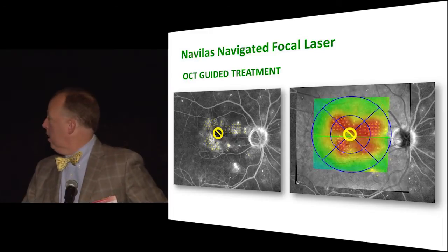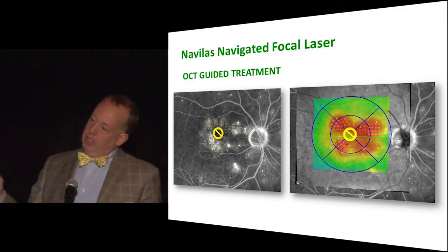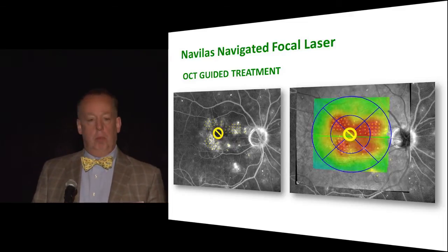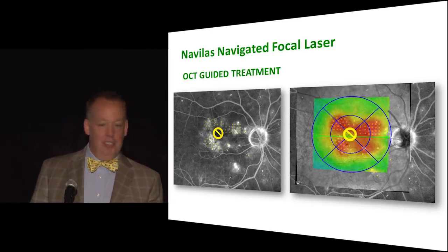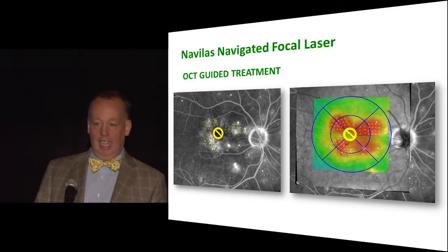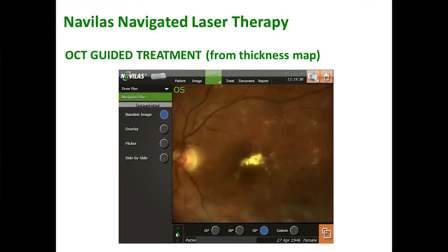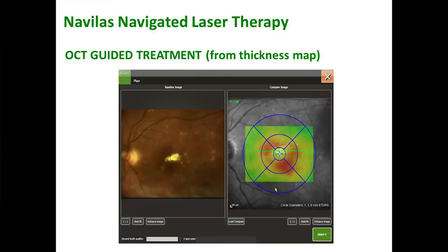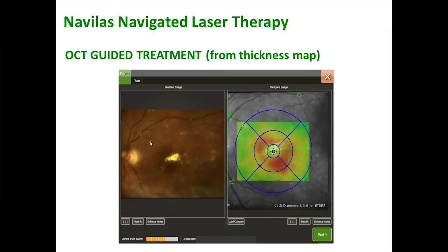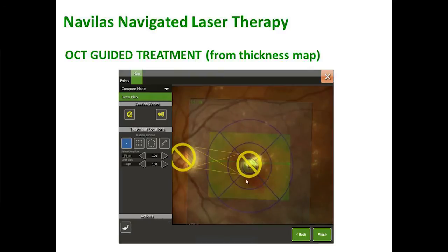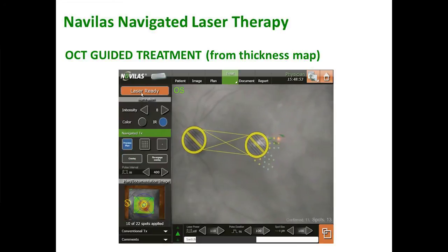More images showing the way you can do a pattern. When you put the fovea block on — in the US at least, and it may be different in Europe — you can actually move the laser and put spots there; it just gives you a visual indicator of where not to put the laser. Outside the US I believe it's a physical block. OCT-guided thickness maps allow you to plan your treatment, showing exactly where you want to go, and you can overlay exactly where you want to miss or where you want to put grid therapies.